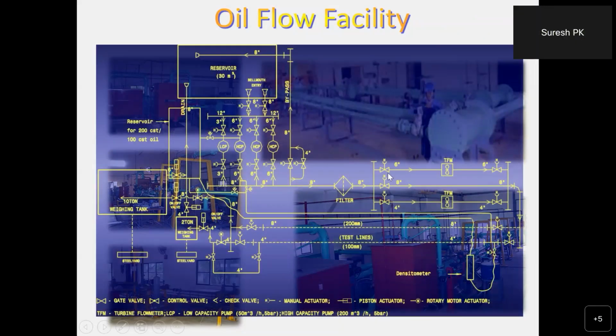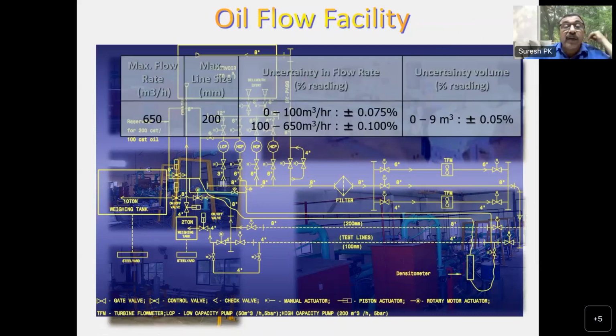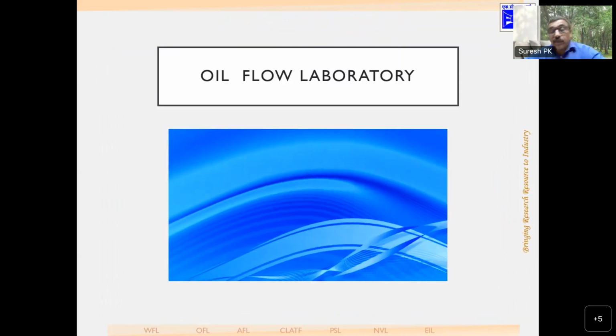Here, you can see that there is a reservoir. The oil which is used is called Exxsol D80, which is very similar to ATF. And you have a flow range up to 650 meter cube per hour. You can calibrate meters up to 10 inch here, with an uncertainty of the order of 0.1%. Uncertainty in volume is better than 0.05%. And you have two test lines, a 200 mm and a 100 mm test line, which can be reduced to any size as per requirement. I'll show you the oil flow lab video.